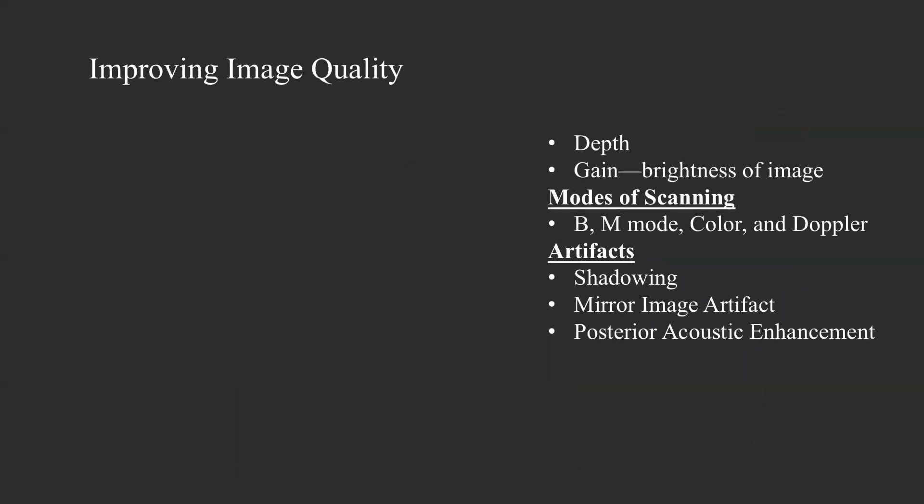To improve image quality, first adjust the depth to focus on specific areas, and adjust gain for better brightness. There are also different scanning modes: B-mode, M-mode (motion mode), color, and Doppler. Additionally, there are different artifacts useful for diagnostic purposes — shadowing, mirror image artifact, and posterior acoustic enhancement. These artifacts help diagnose abnormalities, and adjustments can be made to improve the image. We'll cover these in later episodes.